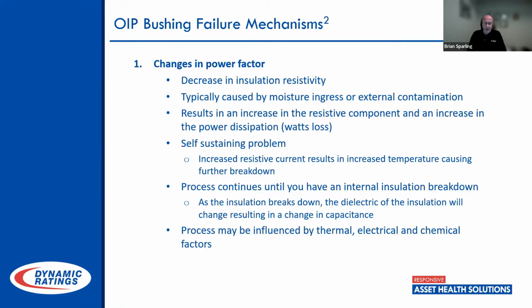We all know that oil and water don't like to mix. So as moisture enters the bushing, it goes into the oil. Oil doesn't want it, but it passes easily into the paper insulation around the bushing. As that becomes more and more wet, the dissipation factor increases, and the resistive currents result in an increase in temperatures, causing breakdown.